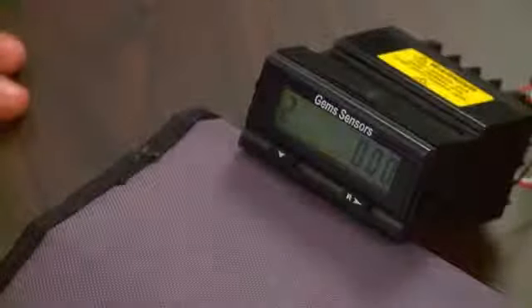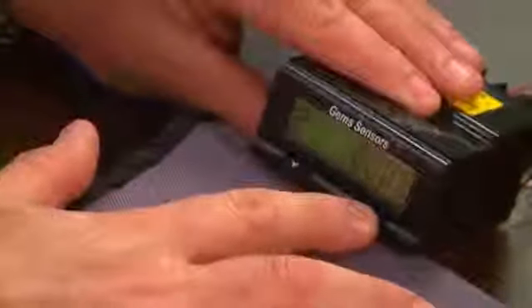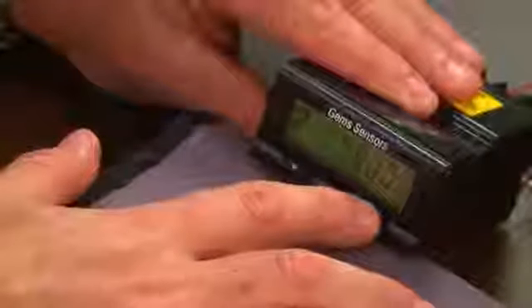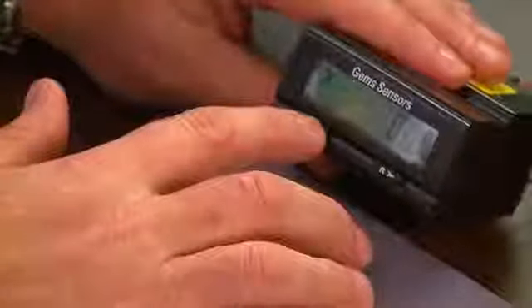Step 2 is where do I want my decimal point for the total? Do I want it to be 1.0 gallons, 1.00 gallons? In this case, I've chosen 2, but again, when you look at the choices, you could choose 3, 4, 5. You could choose none, meaning just count in increments of 1 gallon. Let's leave it where I had it at 2 decimal places. We're done with step 2. We move on to step 3.